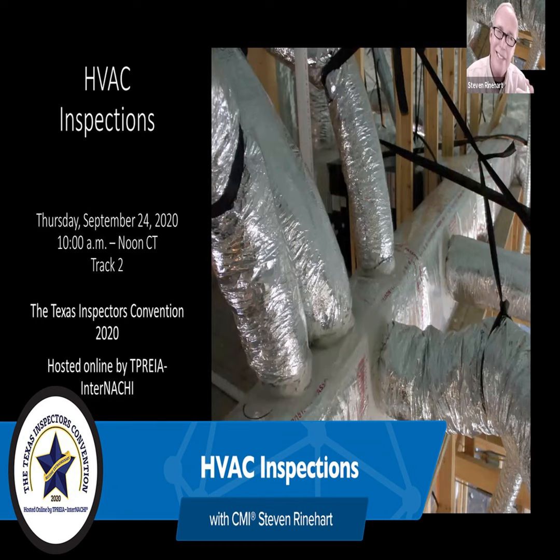If I only got 10 degrees between the intake of the mini split and coming out, I really think, because most of those are like 26 SEER, they're really efficient. They're usually pretty new and clean. You don't find old worn out mini splits. So I think you should still check the temperature. You're supposed to check performance. You need to be able to explain how you check the performance.